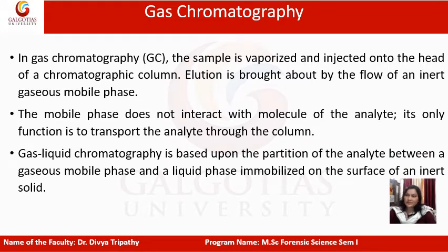Now, what is gas chromatography? Gas chromatography differs from other forms of chromatography in that the mobile phase is a gas and the components are separated as vapors. It is thus used to separate and detect small molecular weight compounds in the gas phase. The sample is either a gas or a liquid that is vaporized in the injection port.